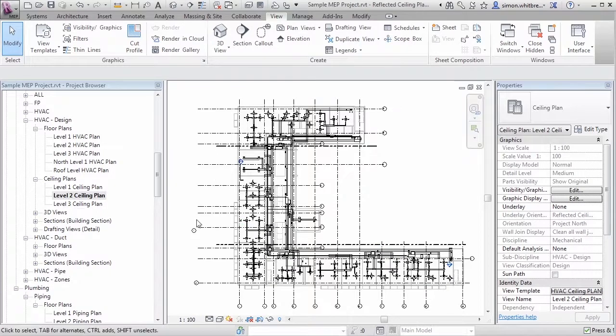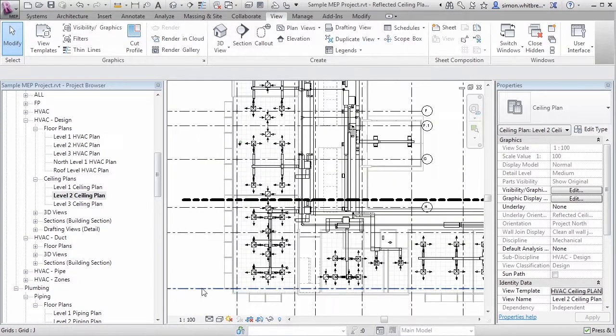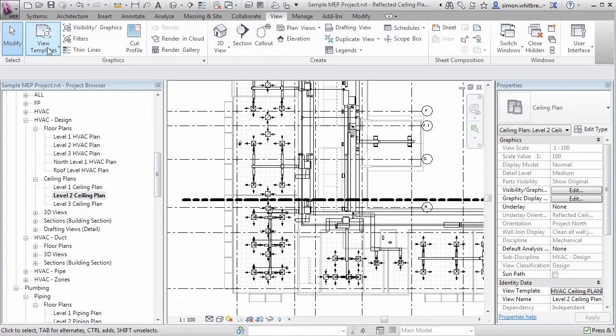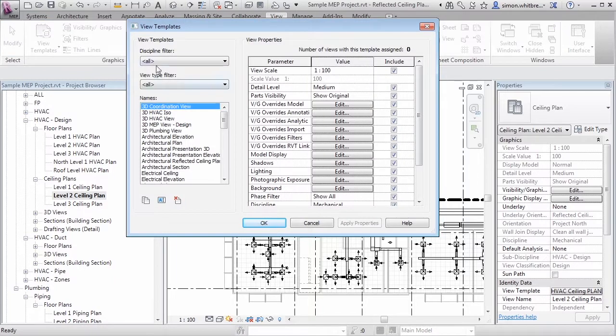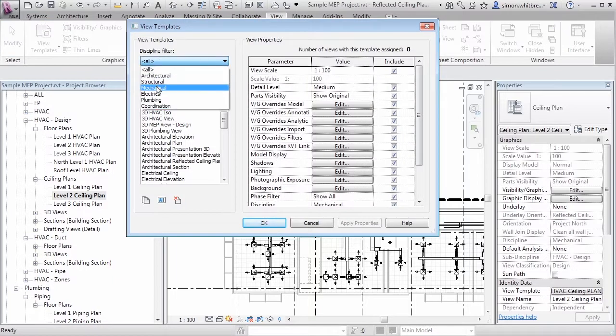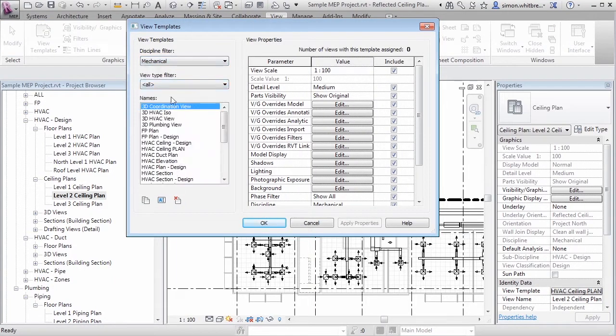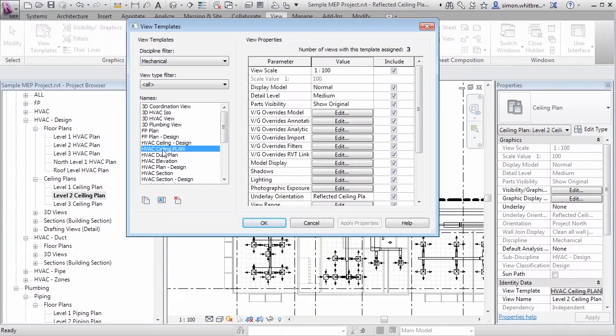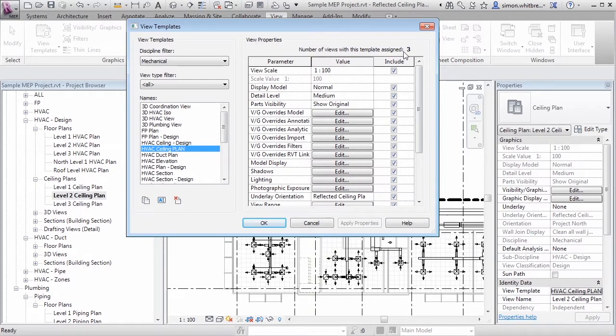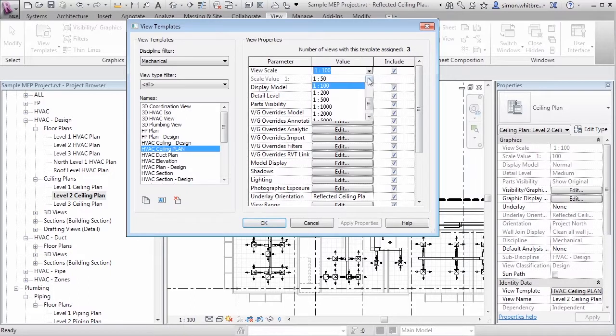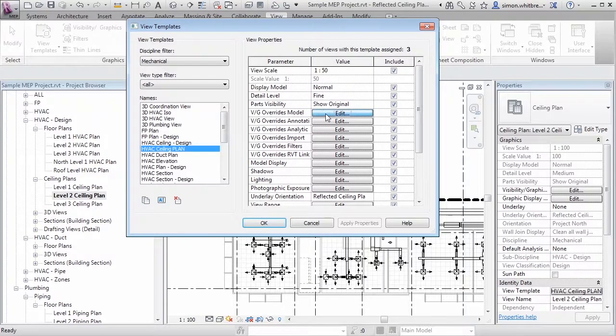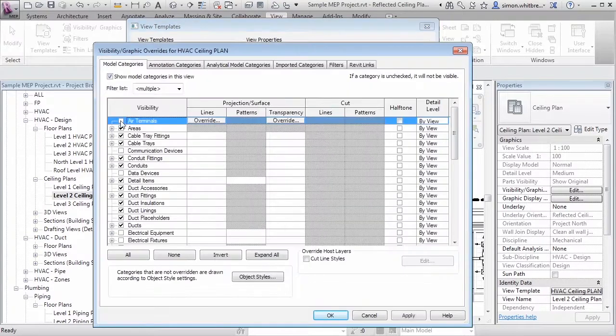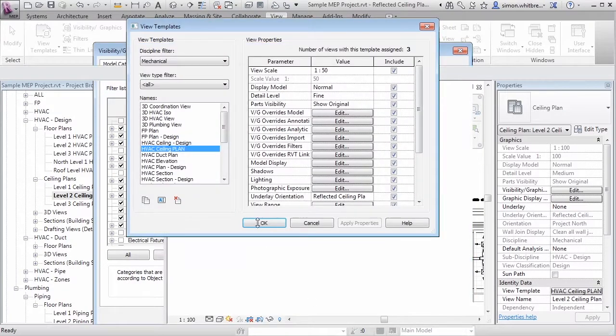If I do want to change them what I need to do is view templates and manage view templates. I can apply a discipline filter so that we just see Mechanical. There's my HVAC Ceiling Plan and at the top right hand side of the dialog box it tells me that we have three views assigned to this view template. So any changes I make here whether it's Scale or Detail Level or Visibility of Objects this will be applied to all three views.